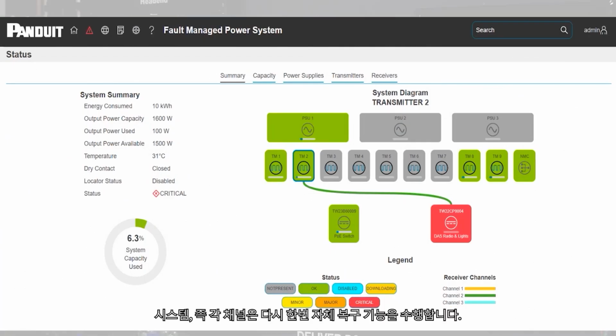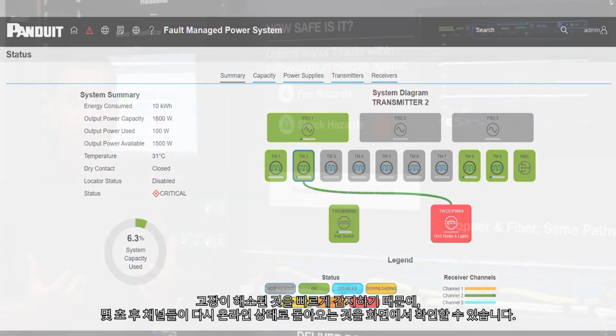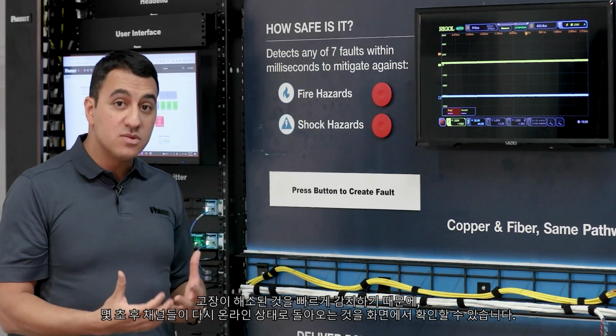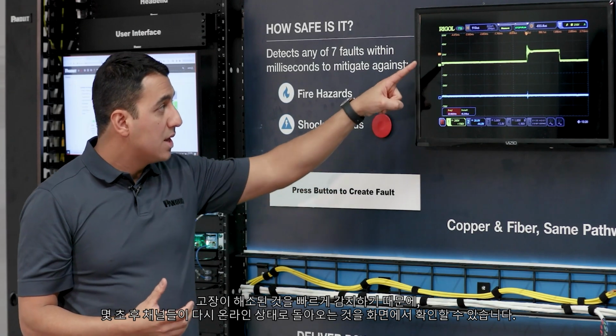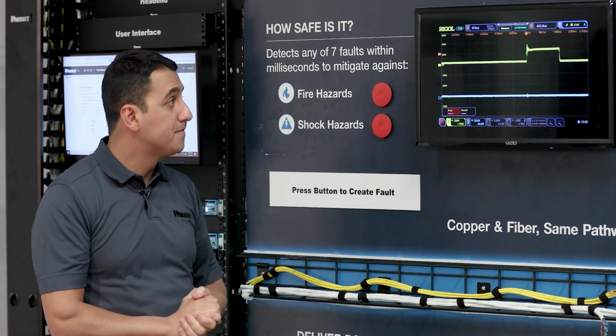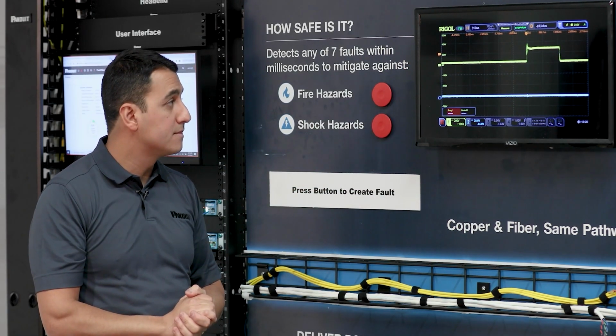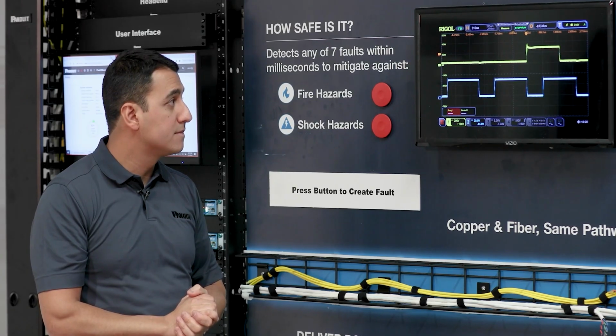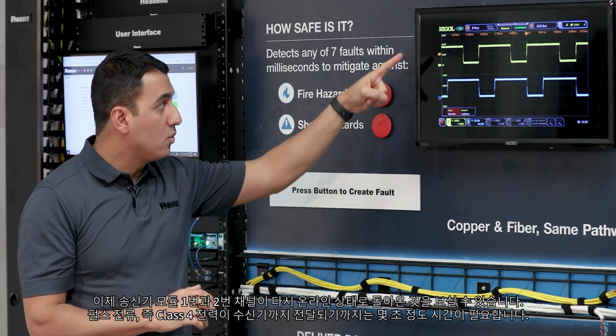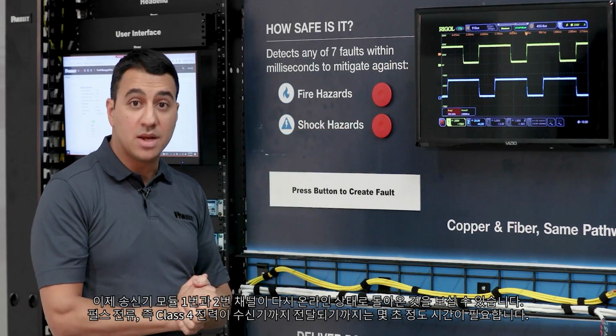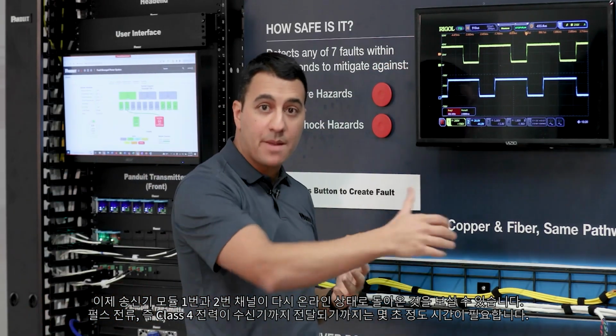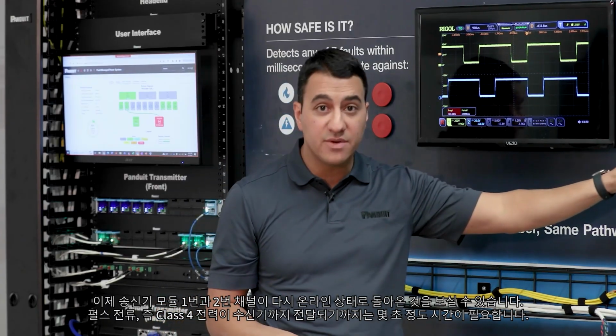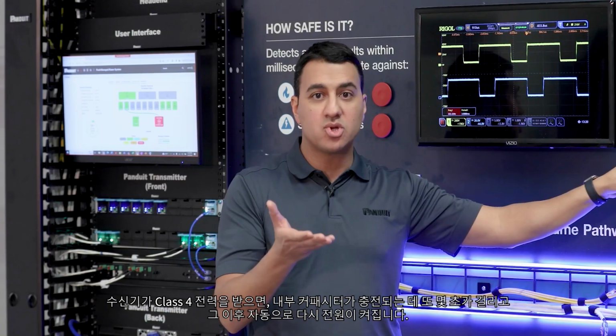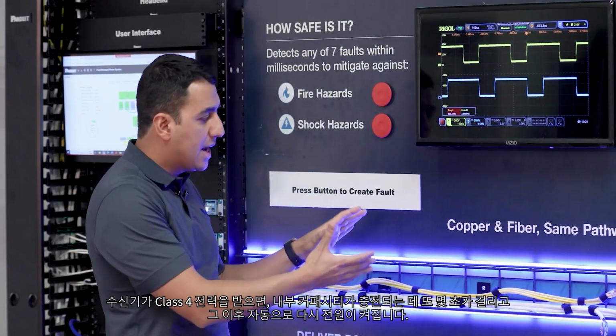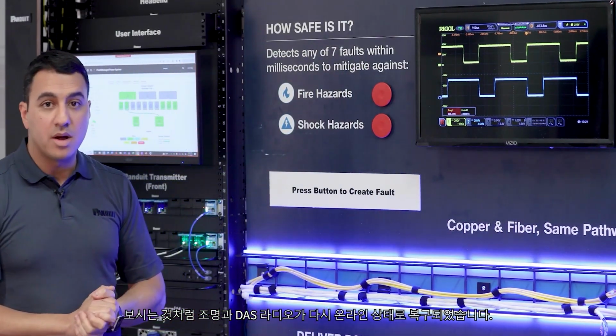The system again, or these channels, are self-healing. They already know that the fault is not there anymore. So it takes them a few seconds and you should be able to start seeing the channels come back online in this screen. Now you can see transmitter module 1 and 2 channels are back online. It takes a few seconds to push that pulse current or Class 4 power out to our receiver. Once the receiver receives that Class 4 power, it takes a few seconds for the capacitor to charge up and then it turns back on automatically. And as you can see, the lights and the DAS radio are back online.